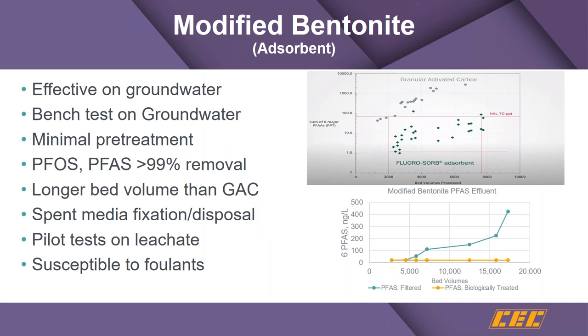These absorbents are pretty effective for leachate but typically require some pretreatment to avoid fouling. Comparing Fluorosorb versus granular activated carbon, the modified bentonite has a strong ability — more so than granular activated carbon — in the groundwater environment. It has a longer bed life than granular activated carbon and comparable capability to ion exchange. Comparing plain filtered leachate with biologically treated leachate, you see a significant difference in how much PFAS is absorbed.